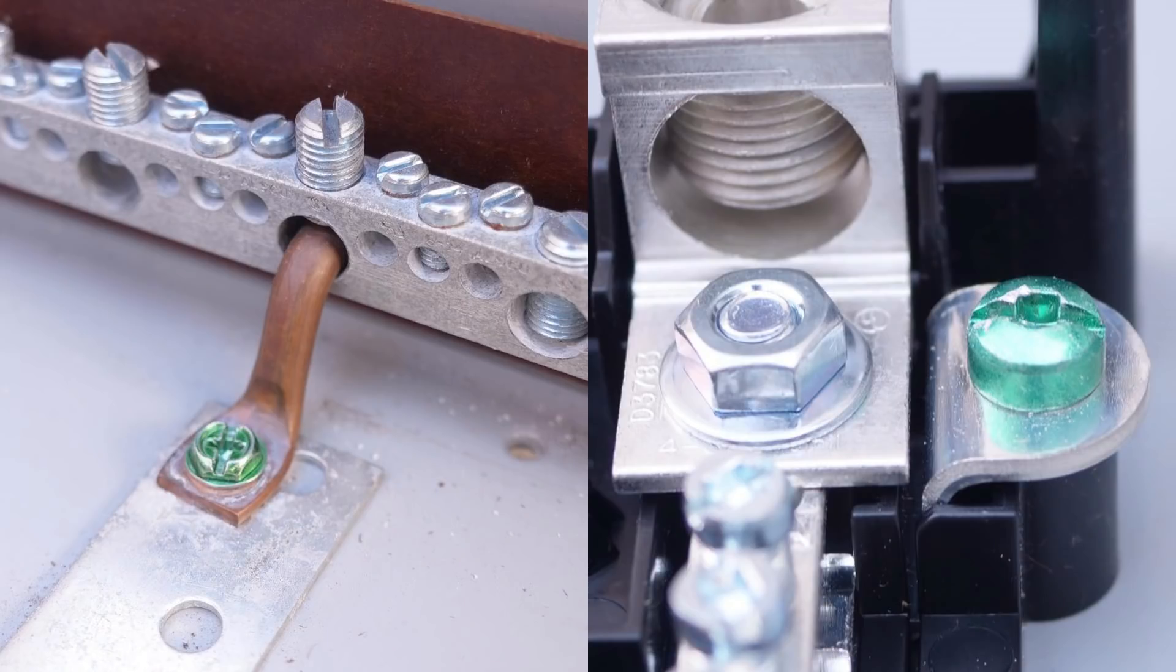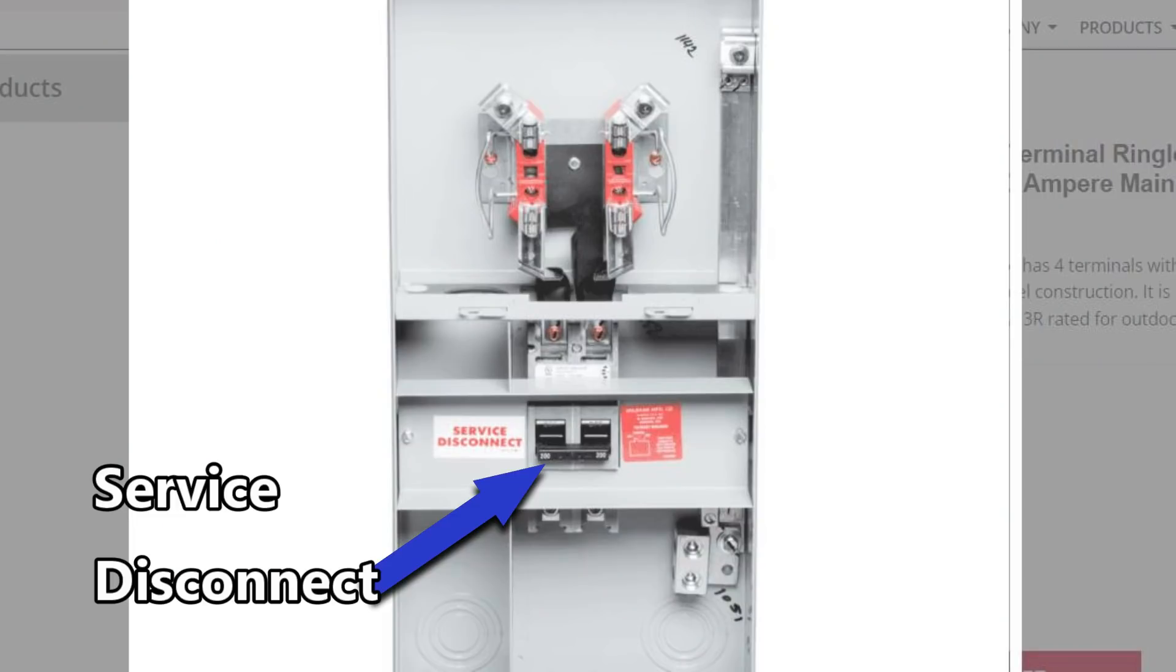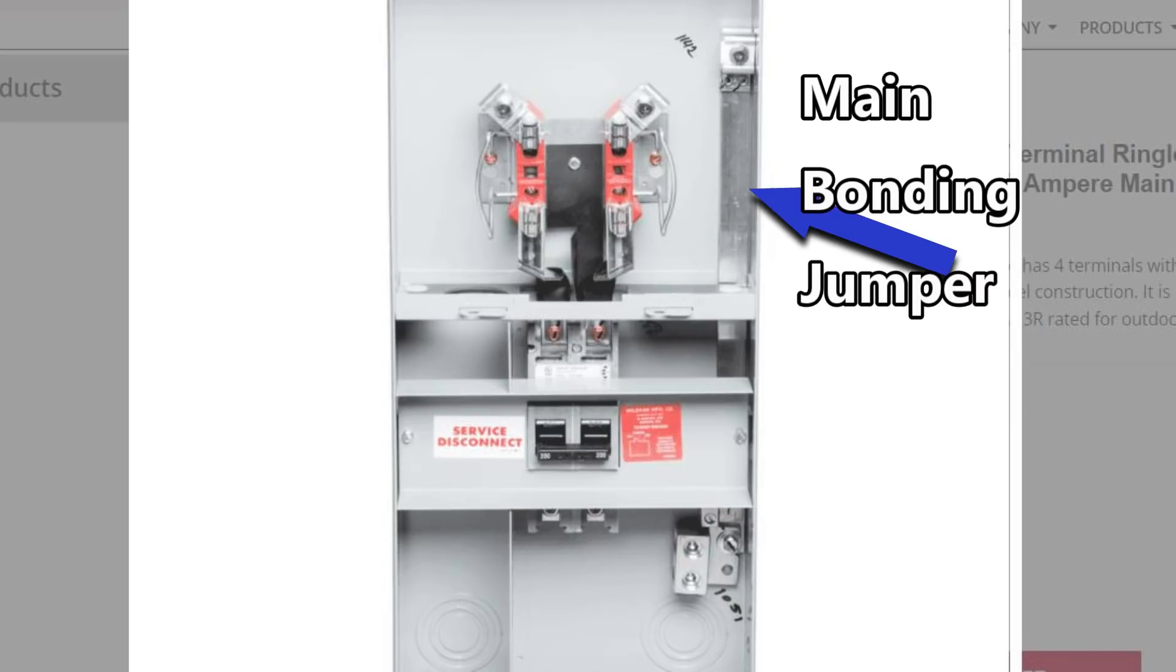When these bonding devices are properly used, they are called main bonding jumpers. Here's a meter socket enclosure with a service disconnect, and here is another example of a main bonding jumper. It comes built in. It connects the neutral lug to the equipment grounding conductor.